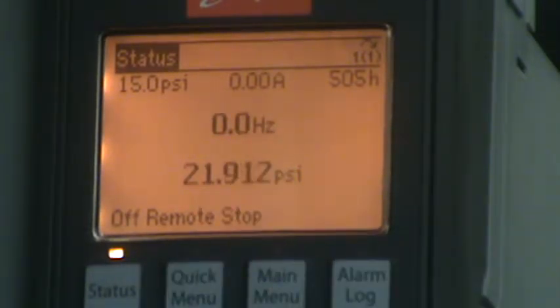Your hertz, it tells you how fast it's going. 18 is locked out as a minimum. You'll never get below that. 60 is the maximum. You'll never go above that. You're going to be able to see, just walking past this over the next couple of years, about where it tends to want to live as the building is occupied and unoccupied. Keep that number in the back of your head for the day something does fail. Put it in hand, you put it back to that number. Yeah, everybody ain't going to be happy, but for the most part, you'll be functioning.